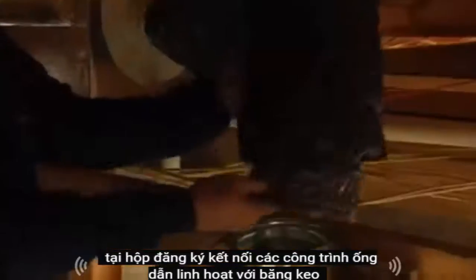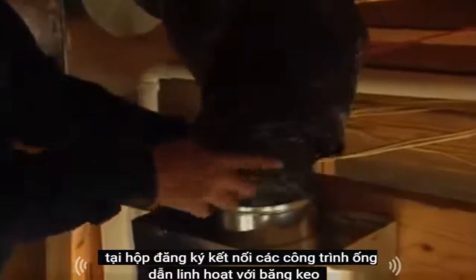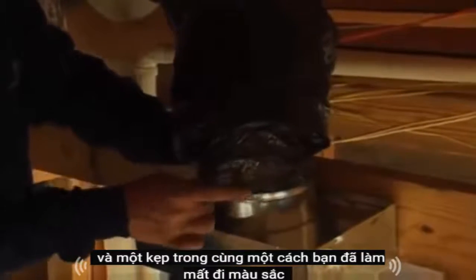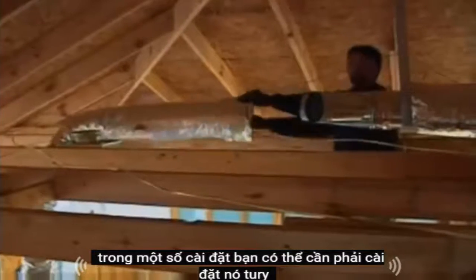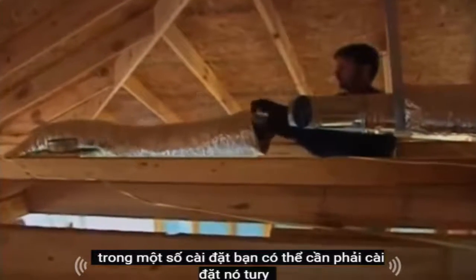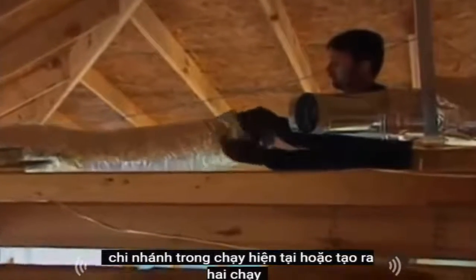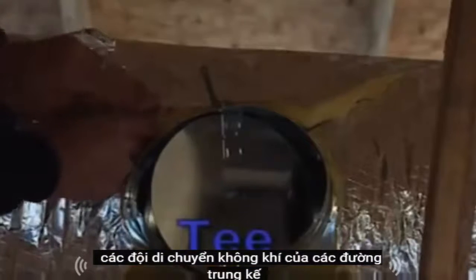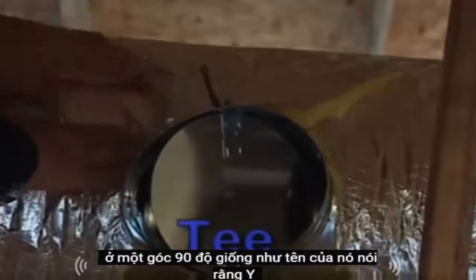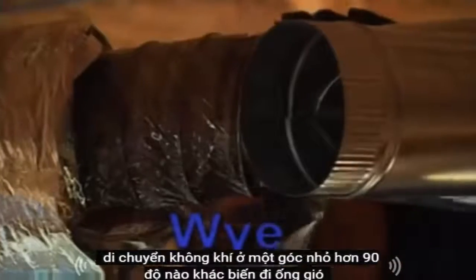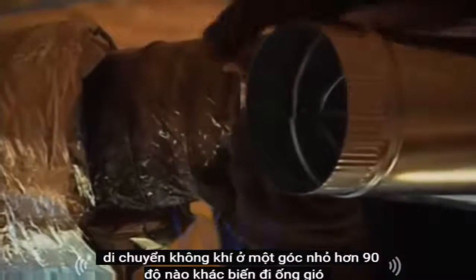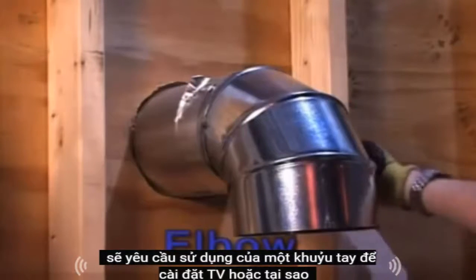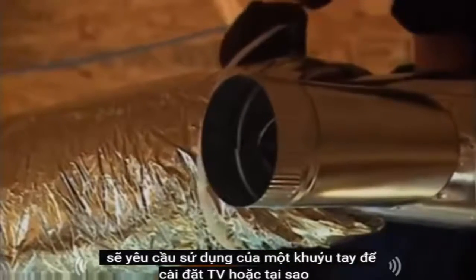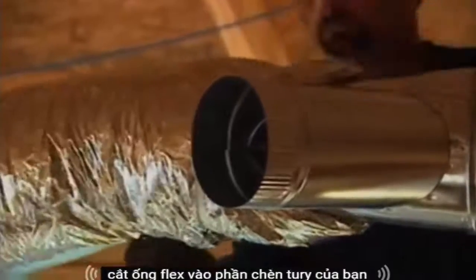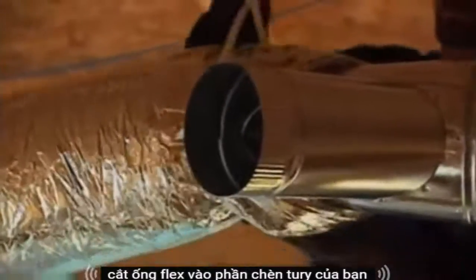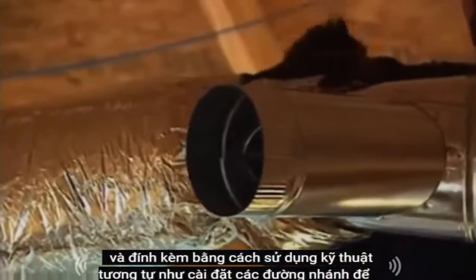At the register box, connect the flexible ductwork with duct tape and a clamp in the same way you did at the takeoff collar. In some installations, you may need to install a T or Y to branch an existing run or create 2 runs. The T moves the air off the trunk line at a 90-degree angle, just as its name says. The Y moves the air at an angle less than 90 degrees. Any other turns in the ductwork will require the use of an elbow. To install the T or Y, cut the flex duct into sections. Insert your T or Y and attach using the same technique as the installation of the branch line to the initial takeoff.